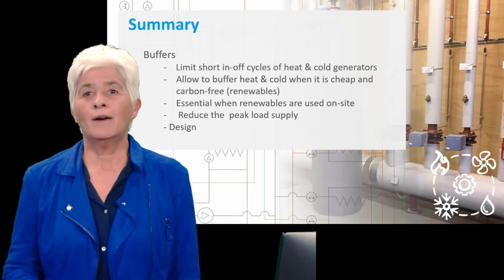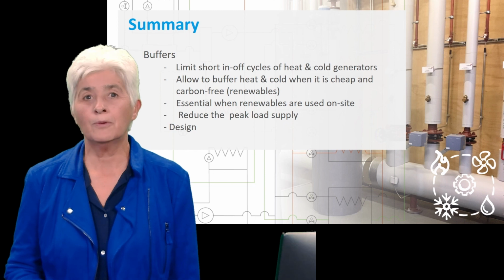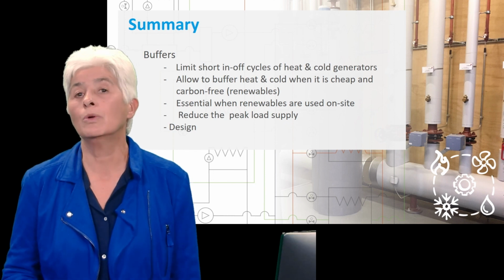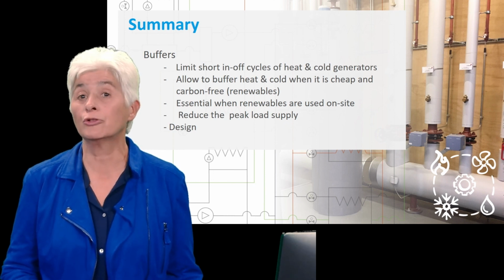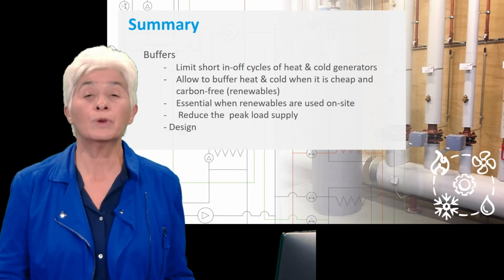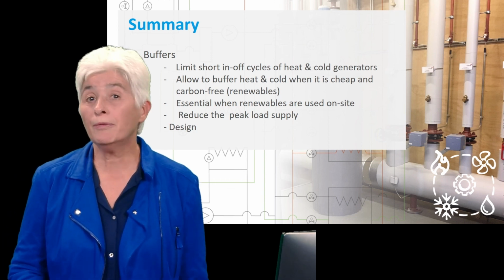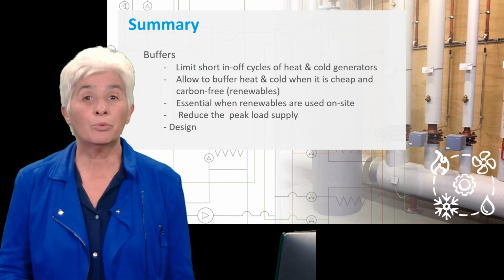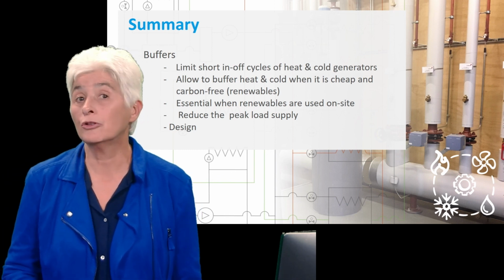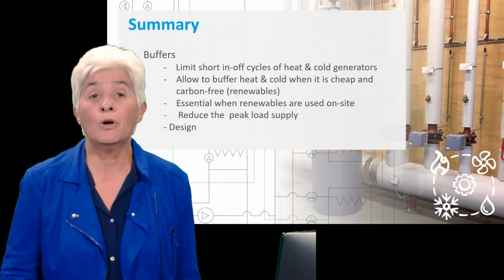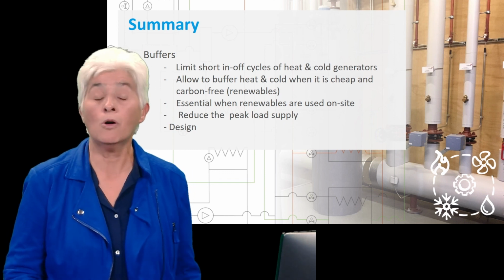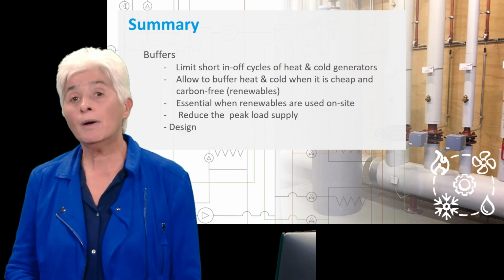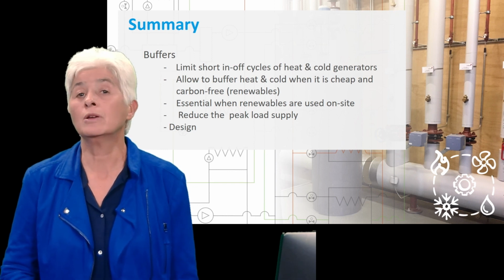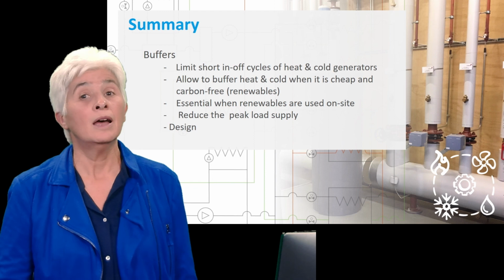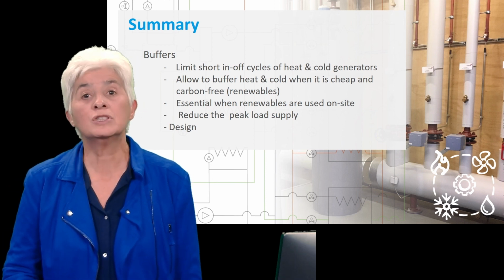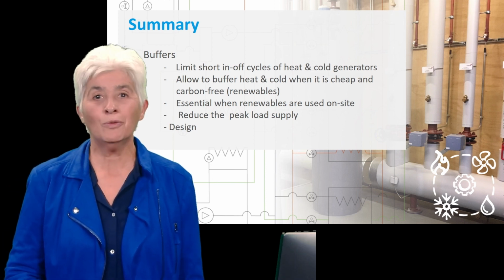In this lecture, you have learned why buffers may be needed. First, they ensure that the mechanical equipment of heat and cold generators does not need to start and stop too frequently. They also allow for buffering heat or cold when the prices are low or when green energy is available, and they therefore avoid the use of too expensive or carbon-rich energy. Buffers are also essential when using renewables for heating and cooling, and finally, they can help with reducing the peak load supply. Thank you for your attention.